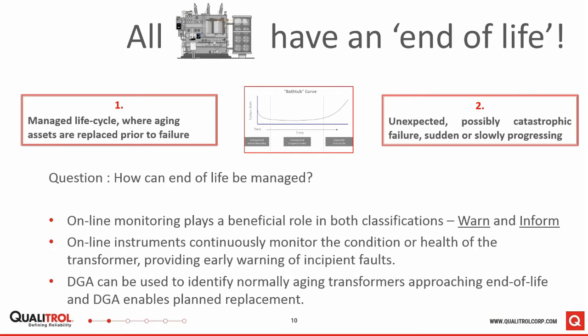Voltage transformers have an end of life. Generally, there are two processes by which they will reach that end. One is they're managed through their life cycle and replaced immediately before the end of life. And the other alternative is that they fail unexpectedly. So how can we ensure that you can achieve the first and avoid the second? What we're discussing and showing here today is that this can be achieved through monitoring and managing the transformer through its lifetime. So as I said before, monitoring won't prevent failure, but it will allow you to manage the asset in an informed way. It won't prevent them from reaching their end of life, but it will warn you when the end of life is likely to be.